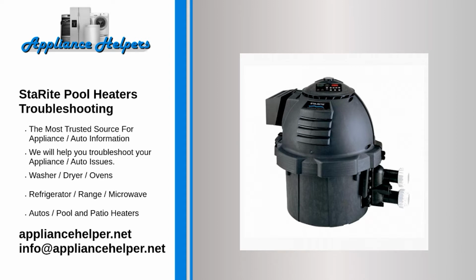First thing to remember is that a pool heat pump can only effectively work in temperatures over 50 degrees Fahrenheit. Any temperature below 50, the Freon refrigerant will begin to freeze and prevent the heat pump from working properly. If your pump is in defrost mode, you will need to wait until the evaporator is free of ice. Is your heat pump located under a low roof or close to a wall or fence? Obstructions may be blocking enough airflow to allow the heat pump to work at peak performance.